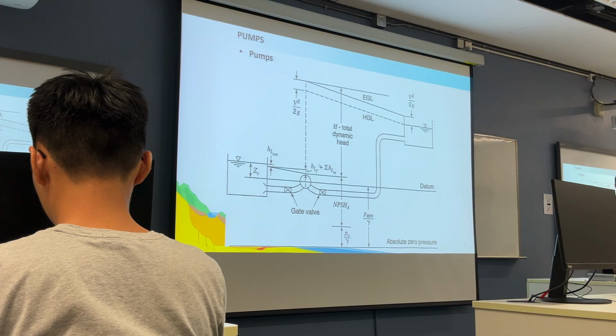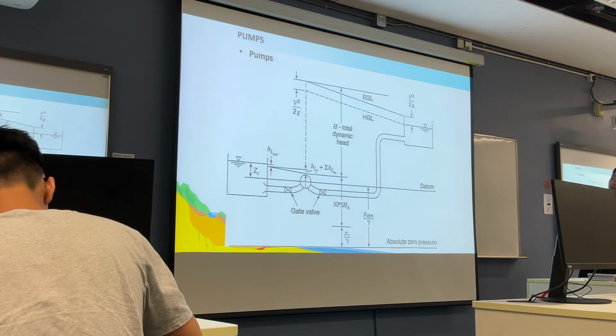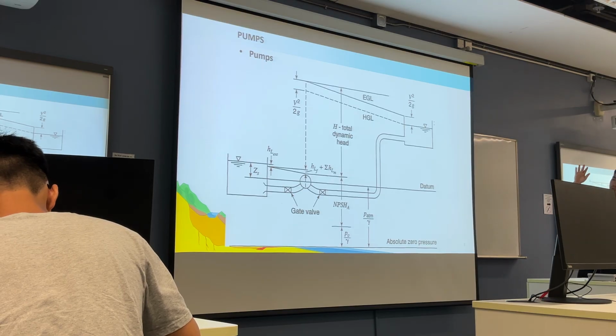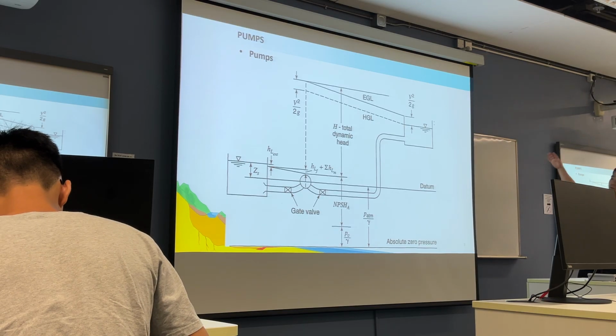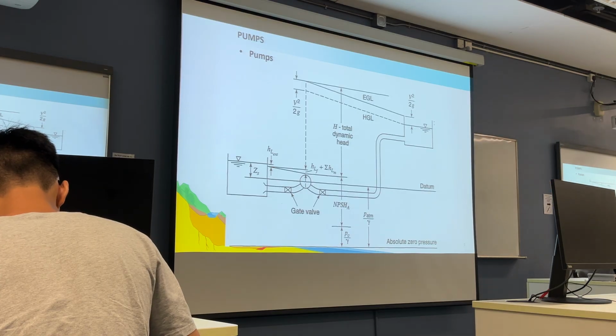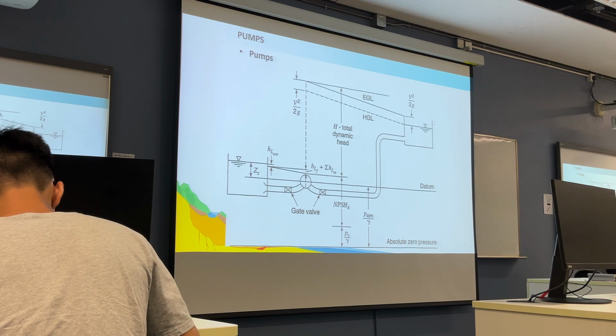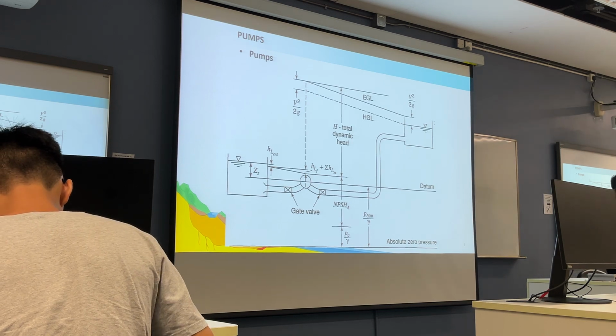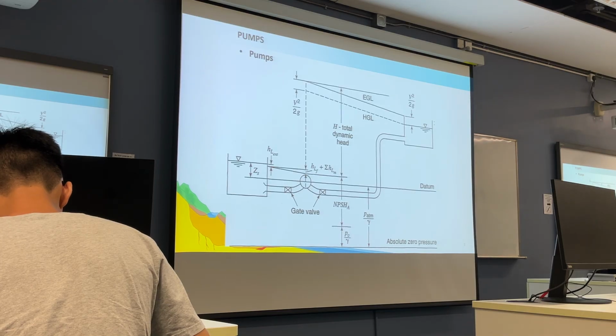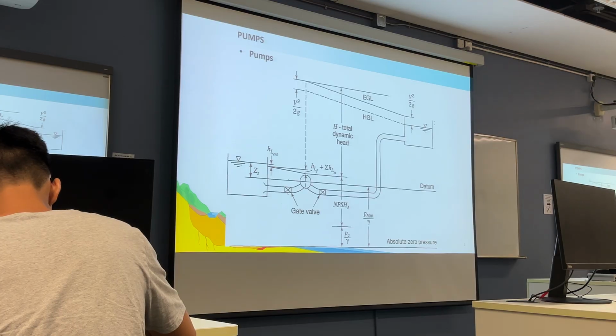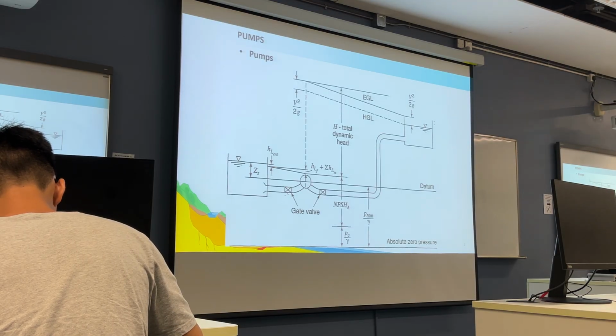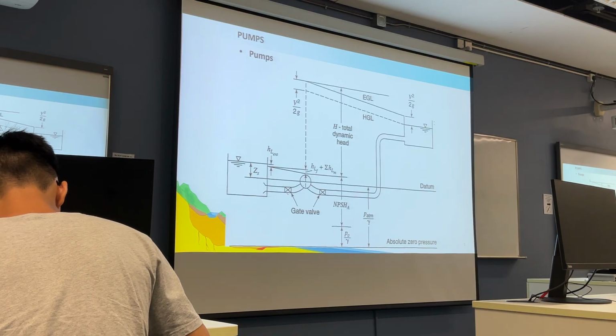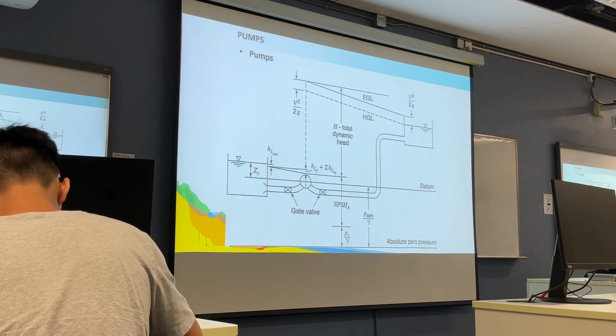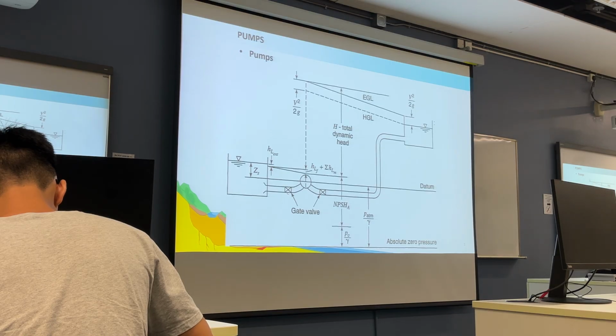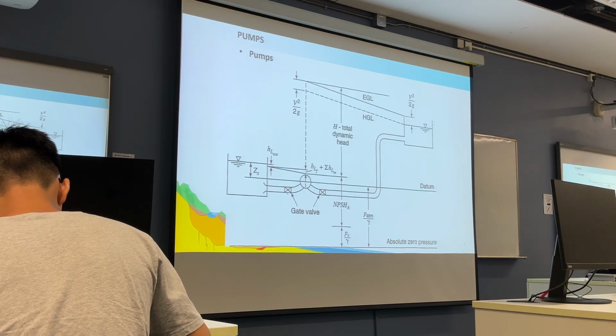Now, let's see a very simple pump system, drawing water from a lower reservoir to a higher reservoir. We will later talk about another thing, which is cavitation. For installing the pump system, you need to consider the cavitation effect. Cavitation is a phenomenon that generates many bubbles, maybe not air bubbles, but vapor bubbles.